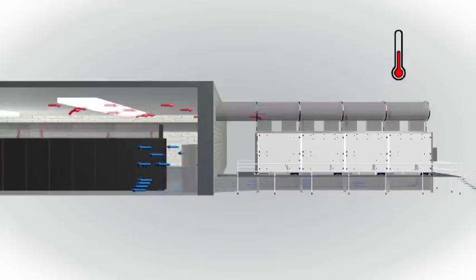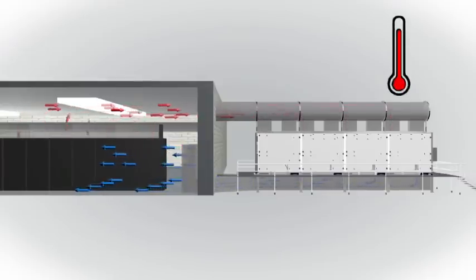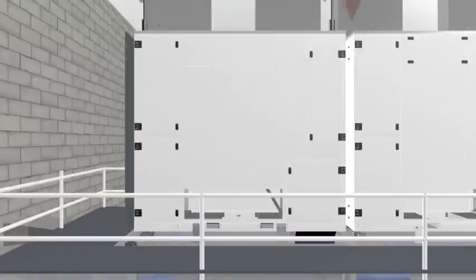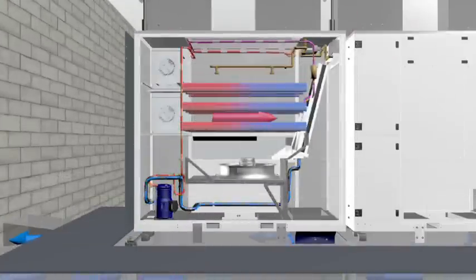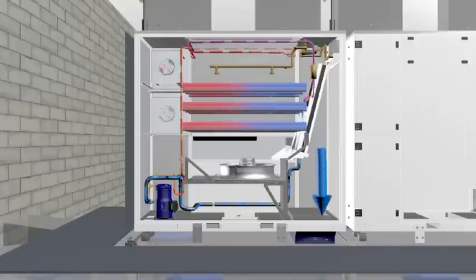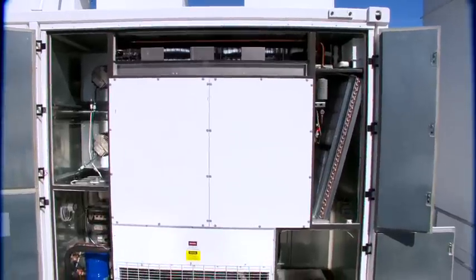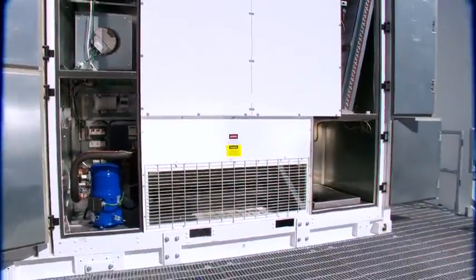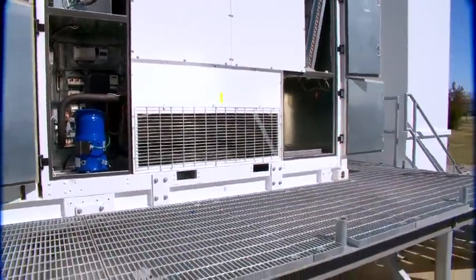And in the worst-case scenario, when the ambient temperature is too hot or too humid to cool the IT air completely, EcoBreeze has a third technology to fall back on, a proportional direct expansion, DX, refrigerant circuit. A proportional DX circuit is identical to what you'd find in a typical air-cooled computer room air conditioner. It's important to have that in there because there will be times of the year where you can't do all of your cooling with an economizing process.